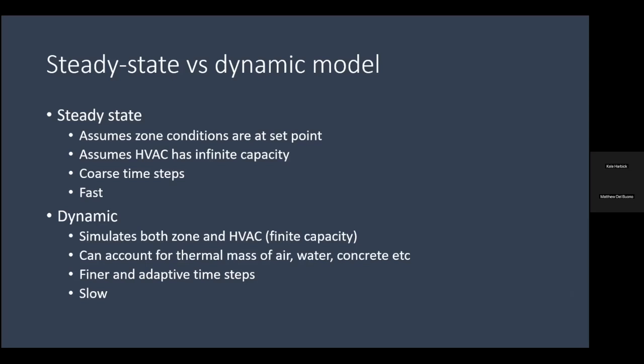In order to do that, you have to assume your HVAC has infinite capacity, that it can handle whatever conditions you throw at it. So you set those conditions, and you calculate what the HVAC system must do to meet them. You usually look at a fairly coarse set of time steps, maybe hourly data. The advantage of this method is it's pretty fast.